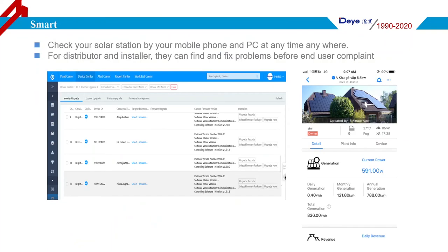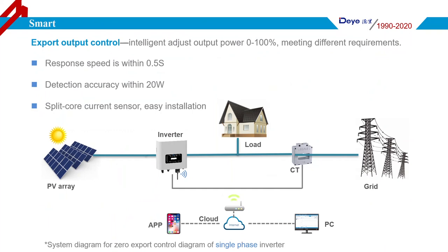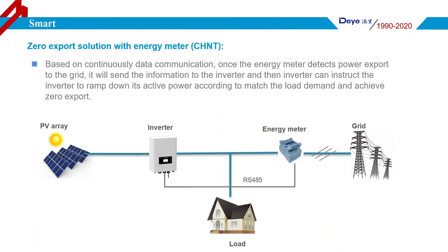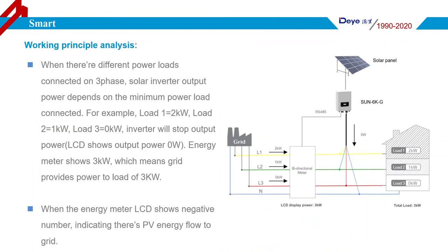All Deye string inverters have an output power control function, allowing you to control output power from 0 to 100% to meet different regional requirements. In many countries where feeding solar energy into the utility grid is restricted, users need to ensure all solar energy is consumed by the local load. For these models with an RS485 interface, the export limit function is easy to implement by installing a CT or energy meter.